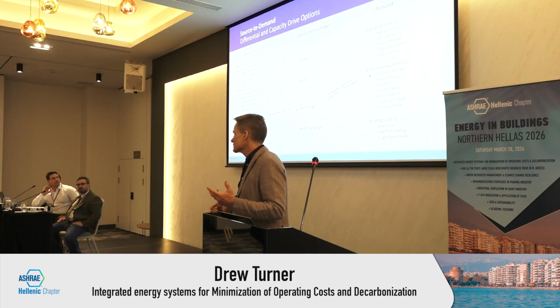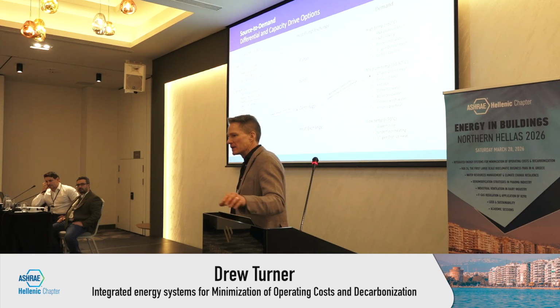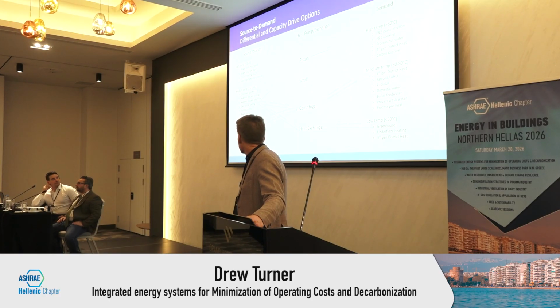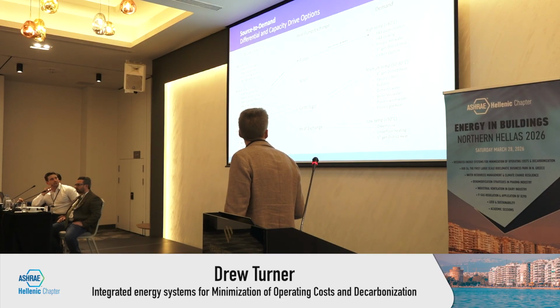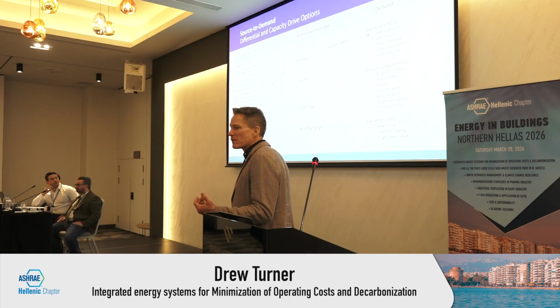When we do this, we try to summarize it in a simple way and say, here's your source, here's your demand, and then ultimately meet in the middle. You start on the outside, you meet in the middle to say what is the best choice of technology to use for the heat pump to meet the requirements of that source and demand and differential and that capacity. These are a few that we worked on. You'll see several different ones, but you start to summarize them in terms of the source and demand temperatures, right? It tells you a lot. What is your optimal source? Your optimal source is going to be your higher temp, but some of these are not necessarily going to be available that often. These are much more commonly available. And then on the demand side, what you try to target is also operating temperature profile changes to those systems.